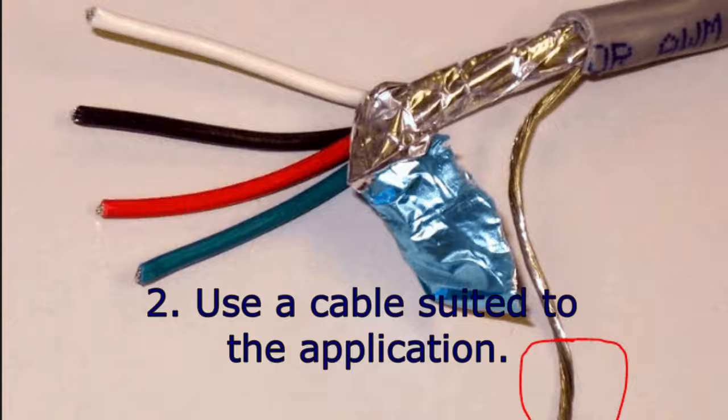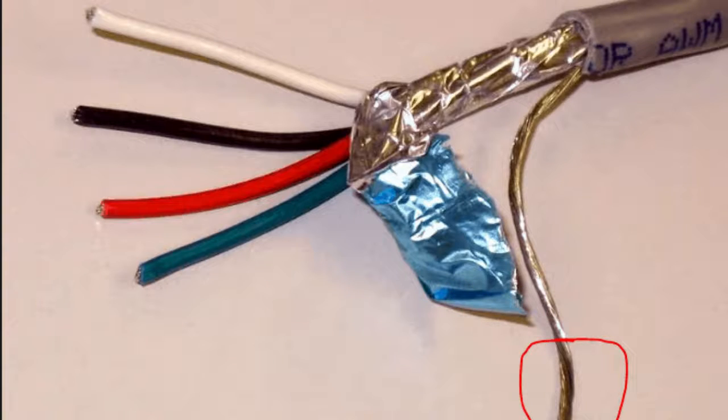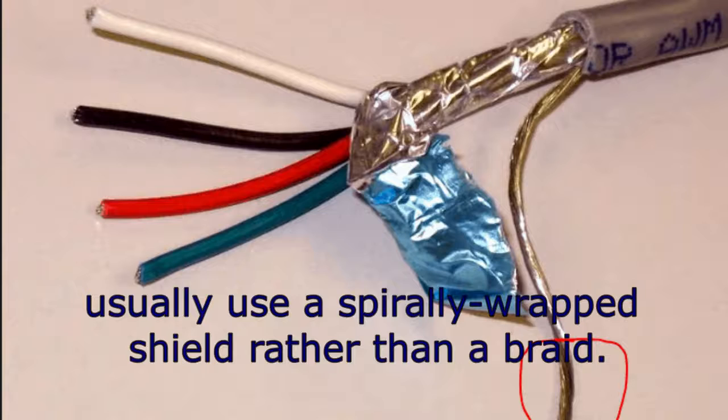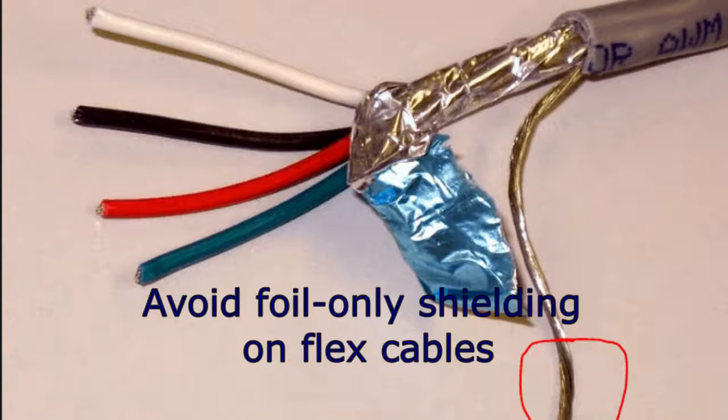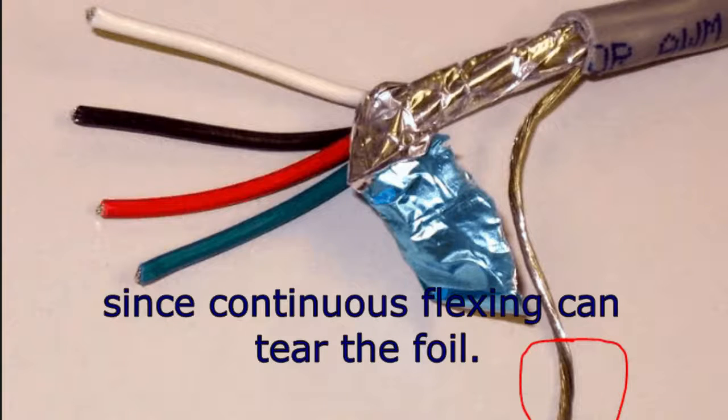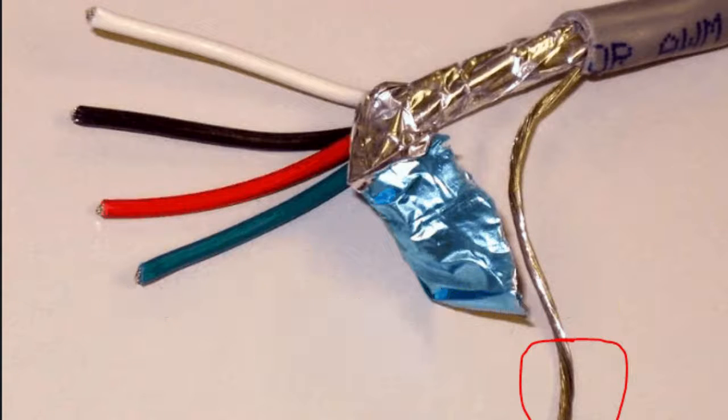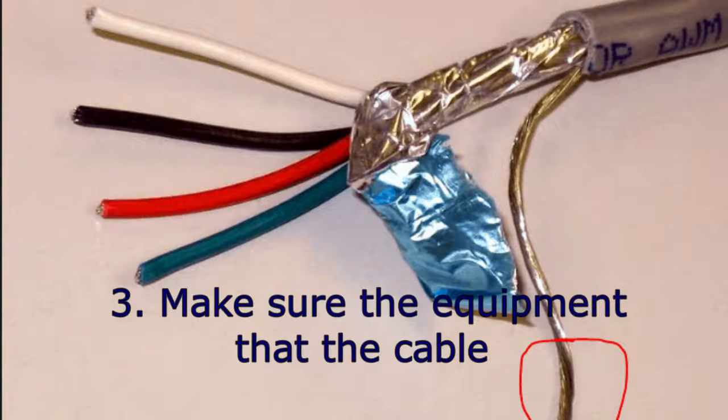Two, use a cable suited to the application. Cables that experience repeated flexing usually use a spirally wrapped shield rather than a braid. Avoid foil-only shielding on flex cables since continuous flexing can tear the foil.